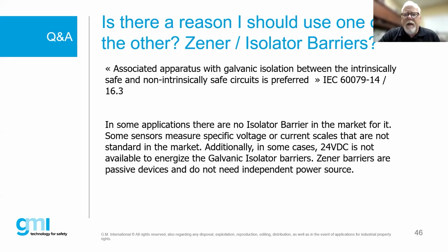One thing I want to add, and I know this isn't a sales pitch presentation: one of the big downsides of traditional galvanically isolated barriers from manufacturers, including GMI, was that they were fairly thick, about 20 to 25 millimeters wide, because there's a transformer on the inside and a lot more devices in the package. Zener barriers were typically much thinner, usually about 12 to 15 millimeters. So one of the big advantages of Zener barriers was the amount of density when putting them inside a panel. GMI's latest generation of barriers shrunk down the width of their galvanically isolated barriers, though they stand a little taller than some competitors' products. But you're able to get that same amount of density using a galvanic versus a Zener. I've run into applications where that was actually a very important point.